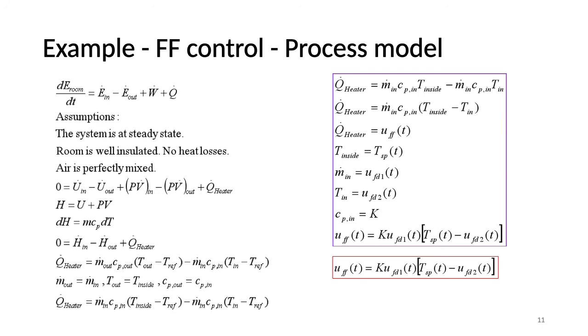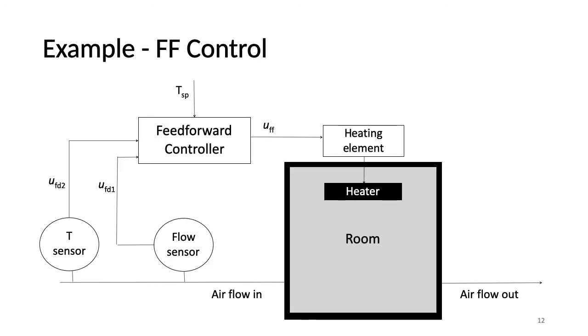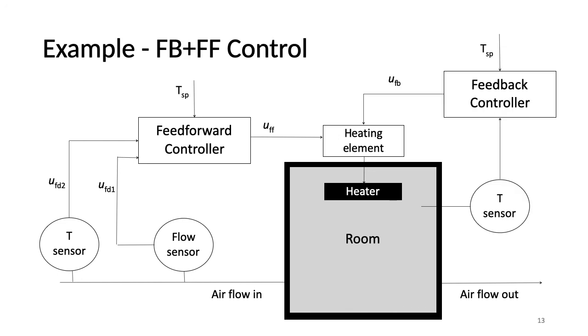Remember that this is a steady-state solution — for unsteady conditions the controller function will be different and more complex. This graphical representation shows the feedforward control system for the room heating process: instead of measuring the inside temperature of the building, we take the desired temperature set point and measure the temperature and flow rate of the air stream coming into the room. This schematic diagram then represents having both feedback and feedforward control systems together, providing much better control than either alone.